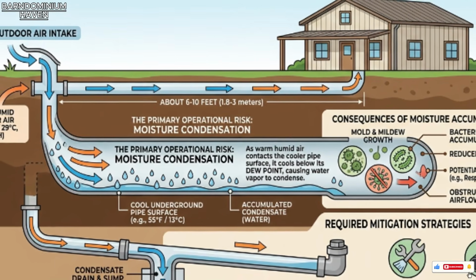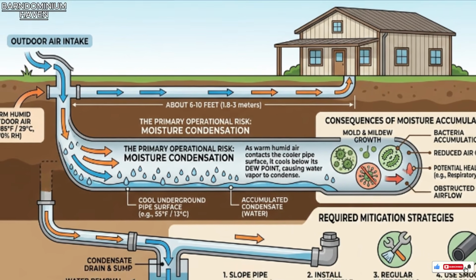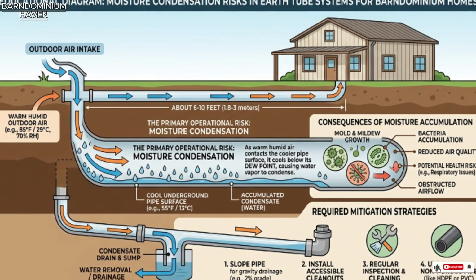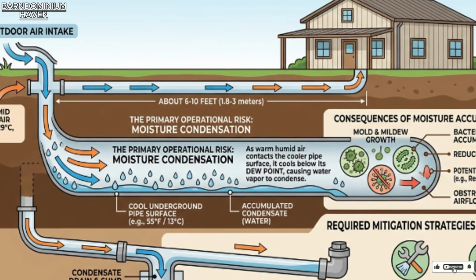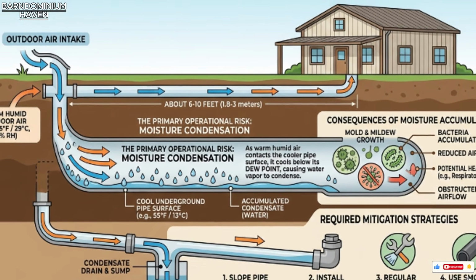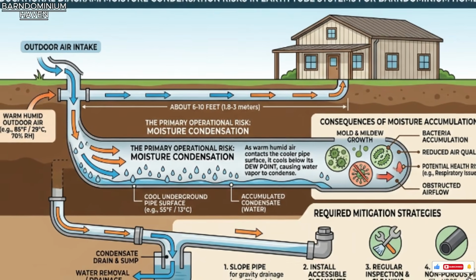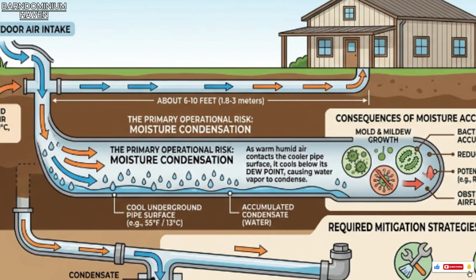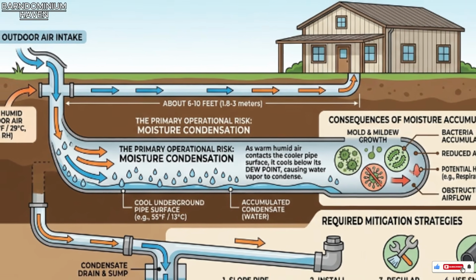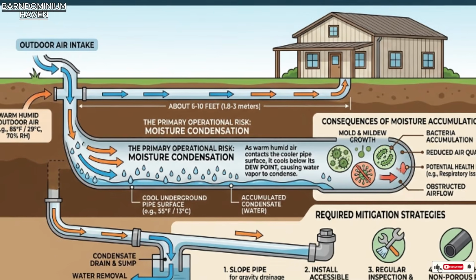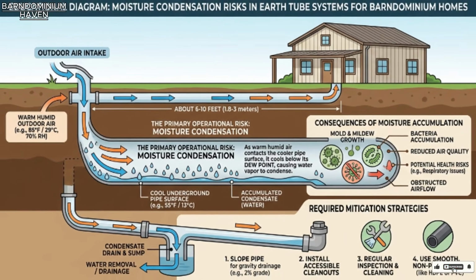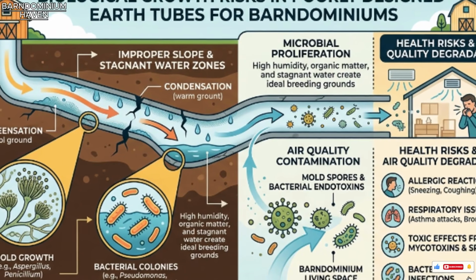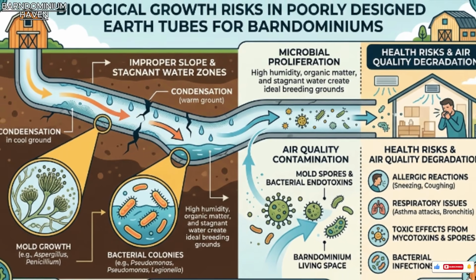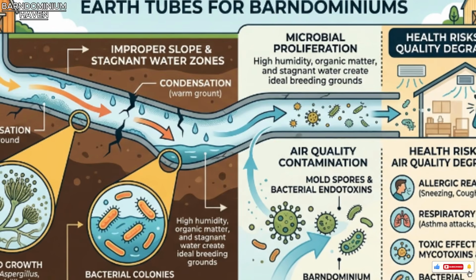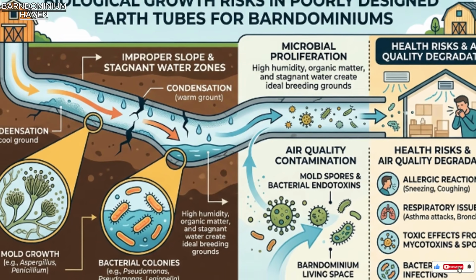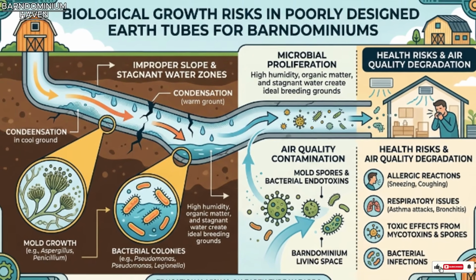The earth tube system is a genuine and proven technology with a performance record that goes back decades in European passive house construction. And it has real limitations that must be understood before any site decision is made. The moisture and air quality challenge is the earth tube's most significant operational risk. Warm humid air drawn through a cool underground pipe produces condensation. And condensation in an enclosed underground pipe creates conditions that support mold and bacterial growth if the system is not designed with adequate drainage, adequate air velocity to prevent stagnant zones, and adequate access for periodic inspection.